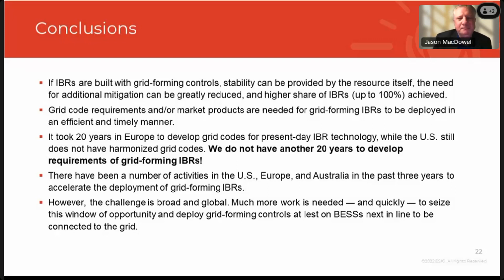What do you think? I think it's a loss of last synchronous machine test. I understand I'm answering a test, not a specification. But I think that's a test that puts you through multiple specifications. So a test of phase jump, it tests inertia and frequency support, whichever way you call it. It tests the capability for power sharing between multiple grid forming devices. So I think it puts you through a number of things at once. So if you can do that, you are grid forming.